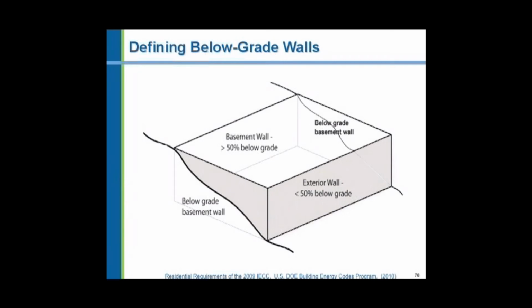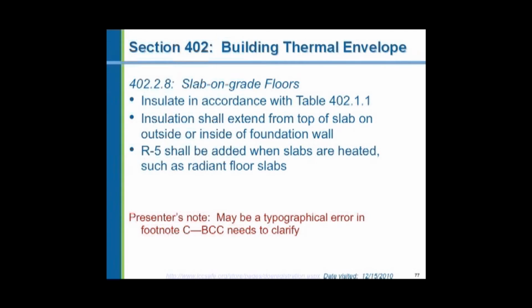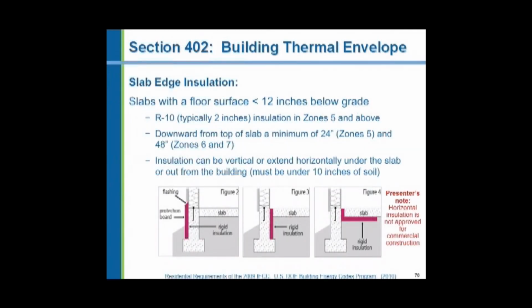And this example, as a walkout basement, has the slab on grade insulation to be installed along the outside of that outside wall. And we have to insulate even more in a slab on grade floor if it's a heated slab. If you install hot water radiant heat in the slab, or you have underfloor air supply ductwork, you have to put an additional R5 in that slab. And here's 3 methods of installing insulation in a slab on grade floor. Keep in mind that this is probably very rare in residential construction, except where you have a walkout basement.